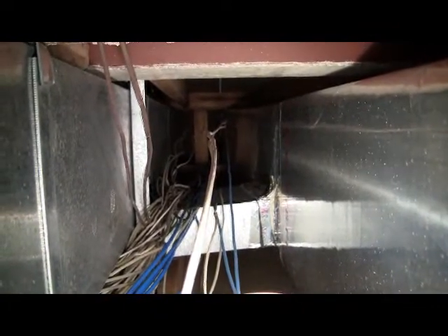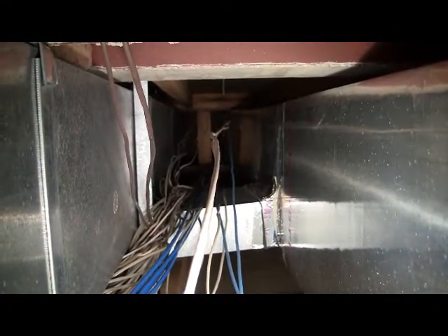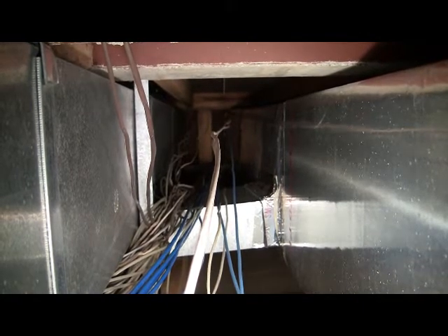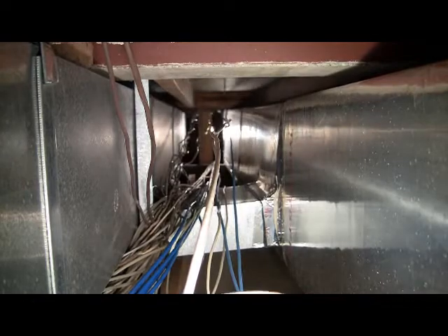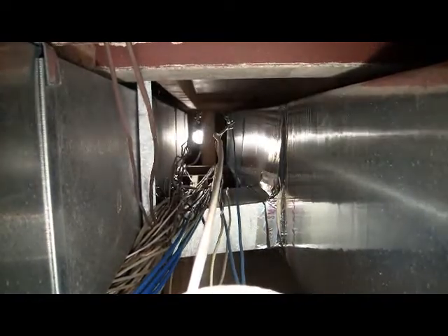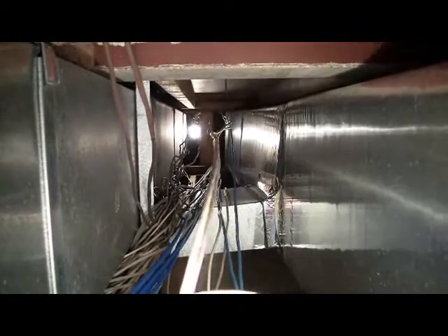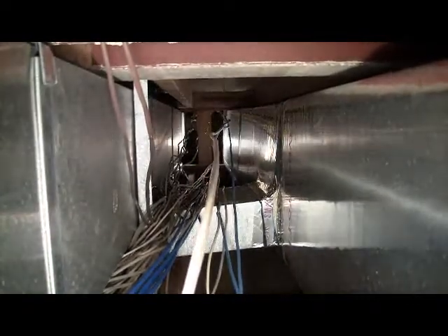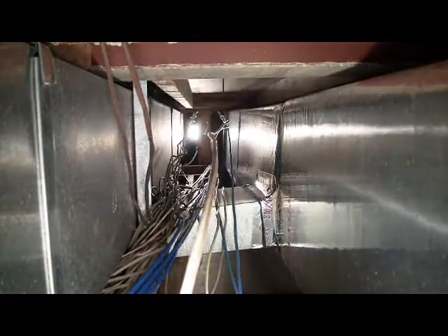So the building cavity itself is an open cavity to the attic, allowing combustion air or any kind of unconditioned air from the attic to be engaged with this basement. We really need to seal the top of this duct so that air that's warmed on the inside doesn't rise because of its warm buoyancy and leak out that hole into the attic.